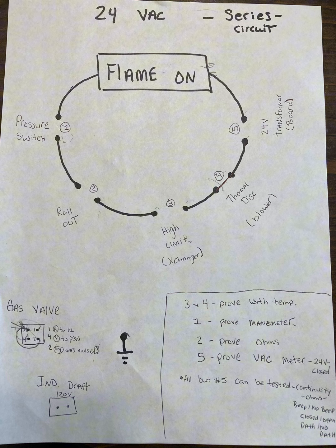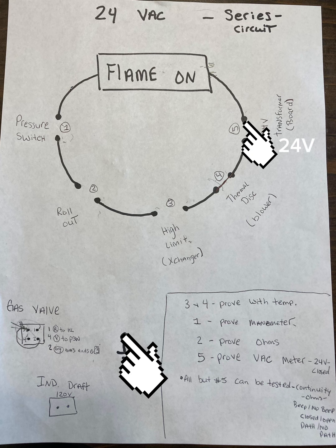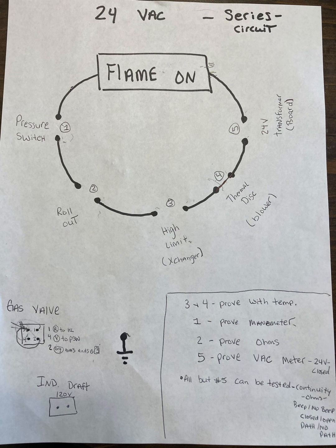The last station on our roadmap is actually coming directly from the control board. This is the transformer feeds into the control board, and out of the control board feeds our control circuit. So we can see right here what are we actually getting from the board itself. We're getting that 24 volts somewhere in the ballpark of it, and that's what's supplying our control circuit.